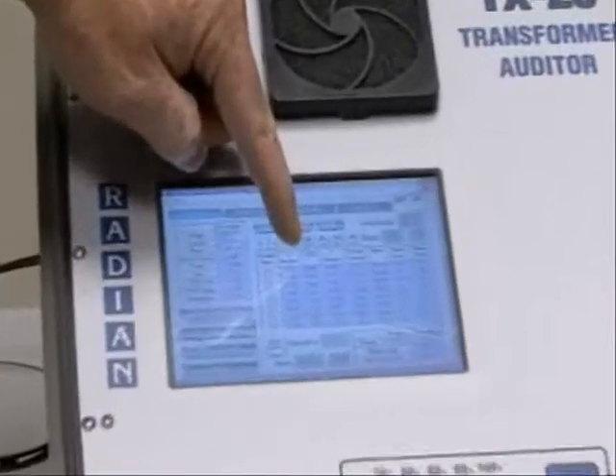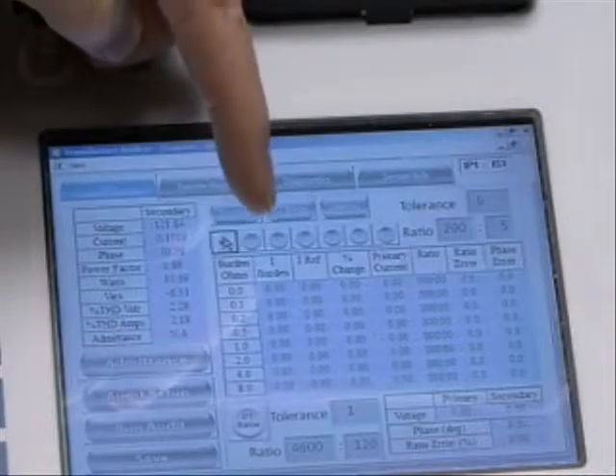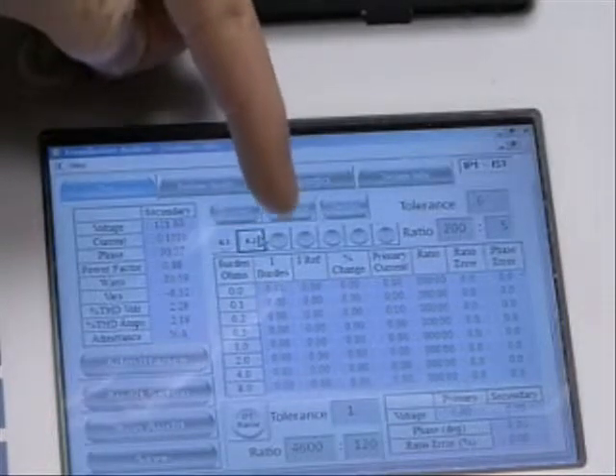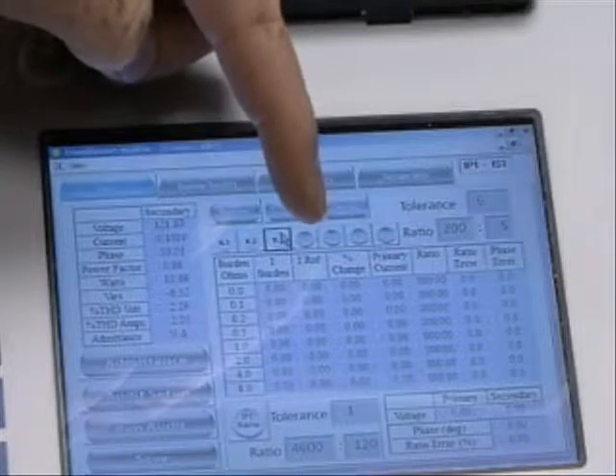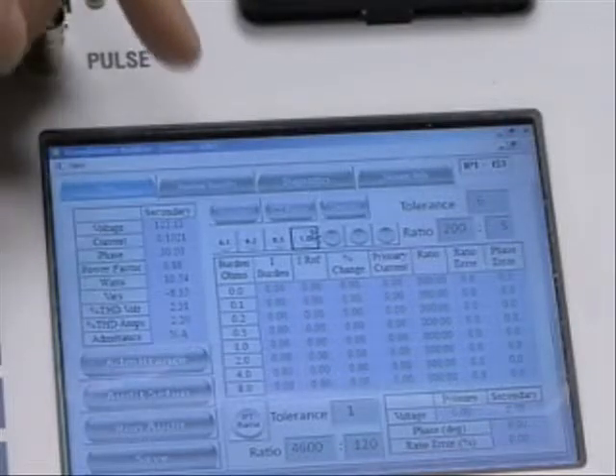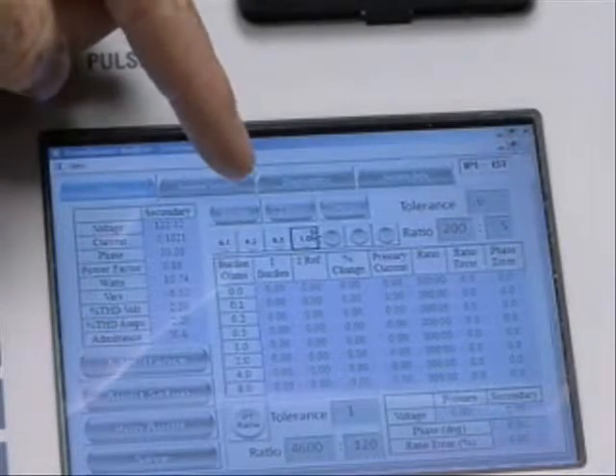And on the TX Auditor, to turn on the burdens, I'm going to turn them off real quick. You simply select the burden, and when it highlights white, it's turned on. Select the second burden, the third burden, and then 1.0 being 1 past the half ohm burden. So all 4 of those burden ohms are selected, and I simply select the burden button to perform a burden test.